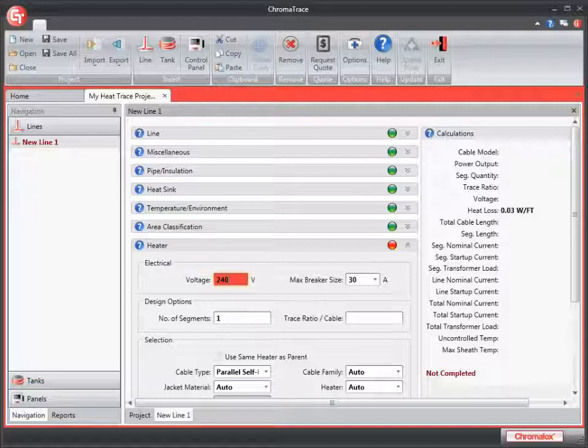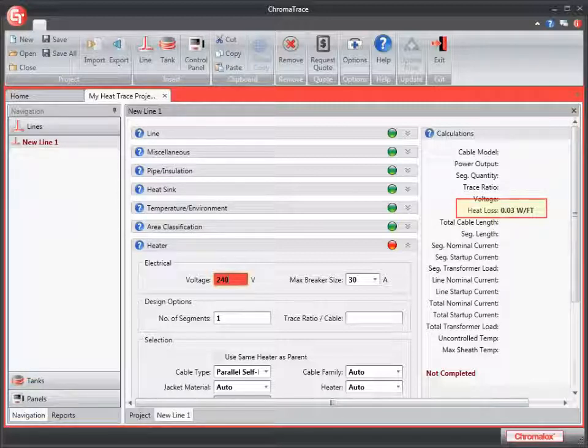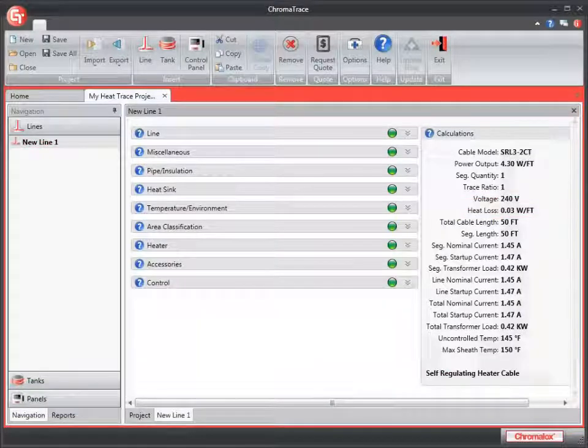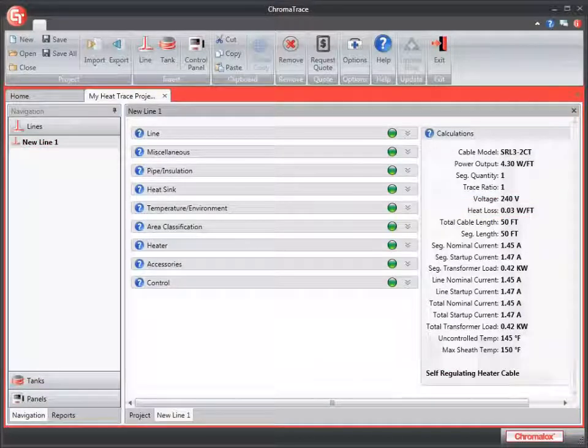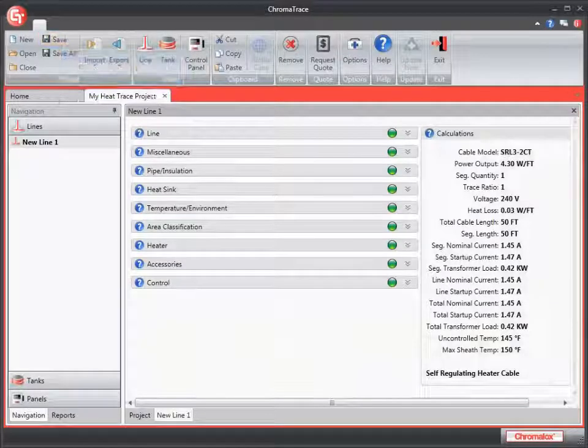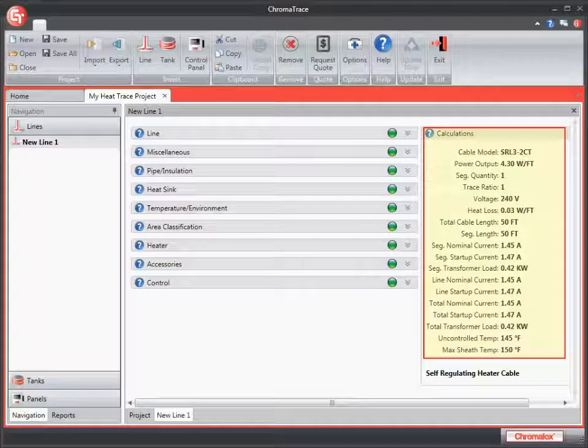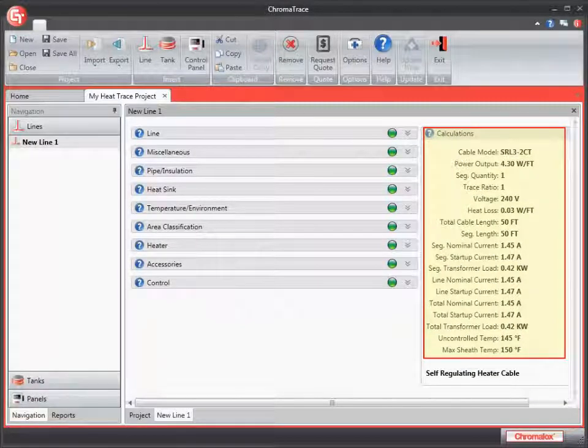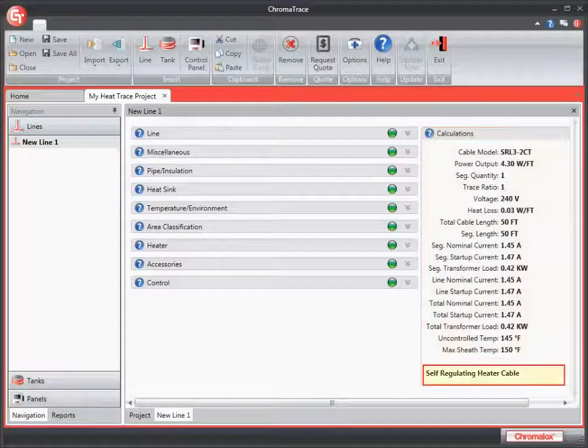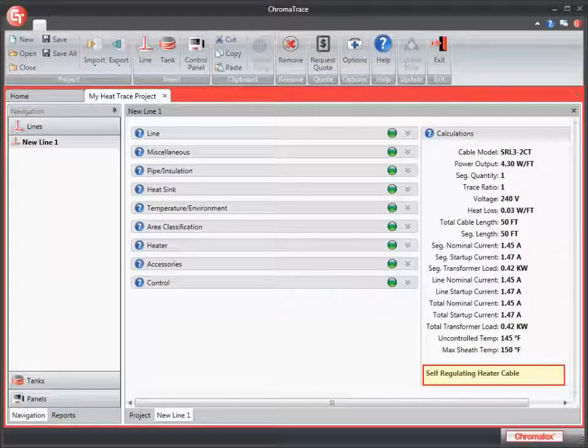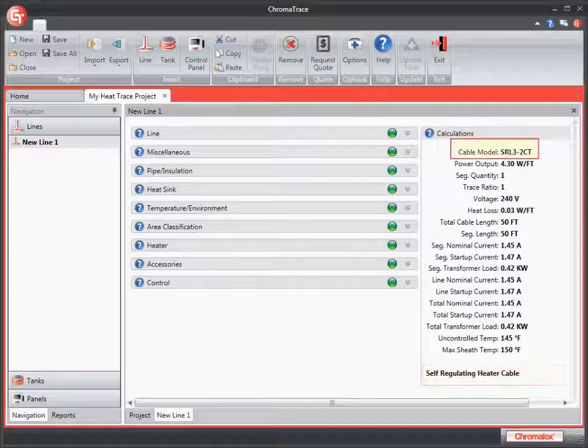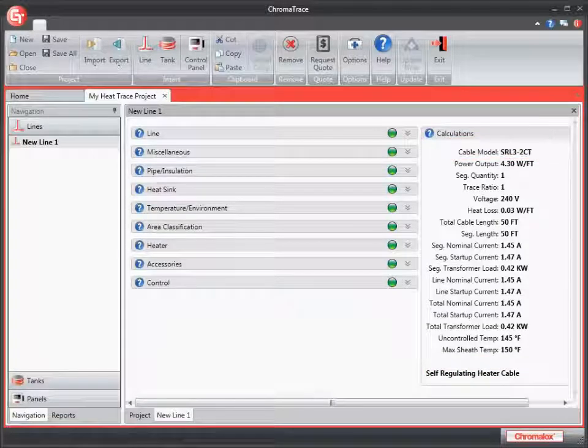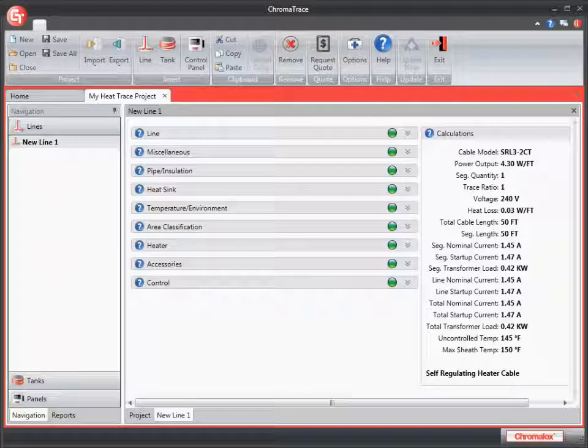And I'm going to save my project now that I have all of my required fields in. I'm going to click the save icon in the toolbar. Look at the right-hand section of the screen under the calculation panel. You see that all of this information is populated based on your entries. And the application is recommending a self-regulating heater cable. Cable model SRL3-2CT. Now I can generate my bill of materials so that I can place the order for my heat trace project.